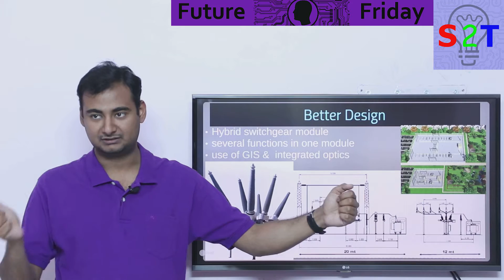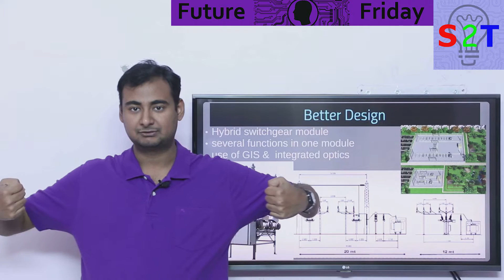When you're talking about gas, you're removing the air and filling that space with one thing, be it nitrogen, carbon dioxide, or SF6 gas. This allows you to pack those components very close together. You have two electrodes, and current jumping from point A to point B becomes very difficult. So in air you have to put them far apart, but with gas insulation you can put them very close and it can't jump because the gas acts as a barrier. We could also do this with oil, and there are some oil variants, but because oil has a tendency to explode when something goes wrong, people don't want to use it as much.